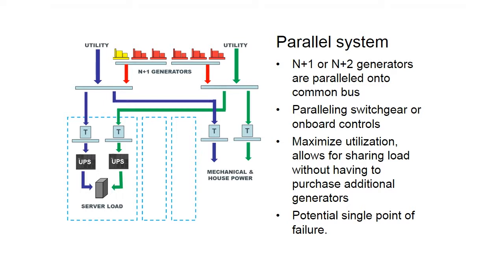These systems typically use paralleling switchgear. More recently, you're starting to see a lot more onboard controls, where the paralleling control is actually with the generator, and then it has a contact that basically connects to a common bus. It kind of eliminates the need for a paralleling switchgear. It comes right with the generator. The big benefit of a paralleled system is maximizing utilization. It allows you to share the load without having to purchase additional generators. So if you have blocks of load that are underloaded, you don't have to buy a whole new generator. You can share the load between the two.